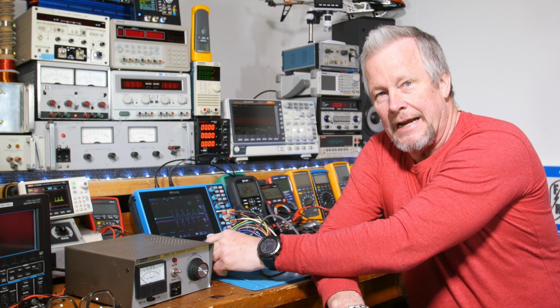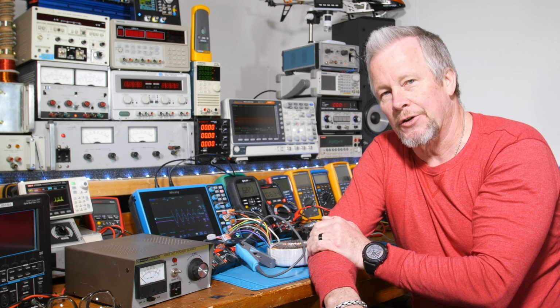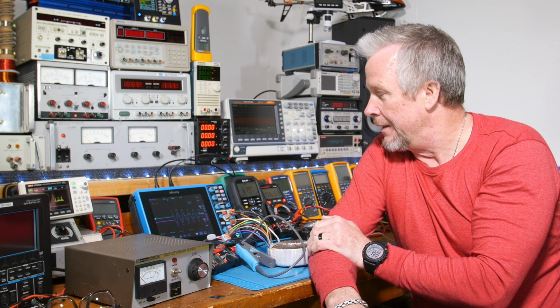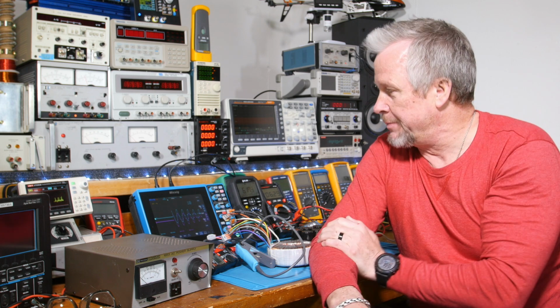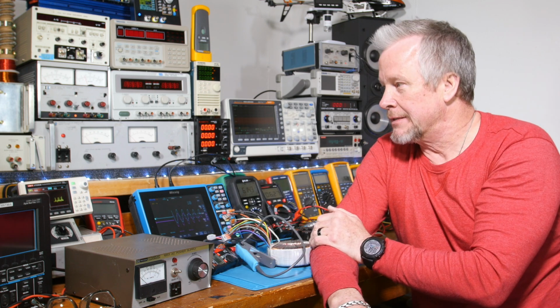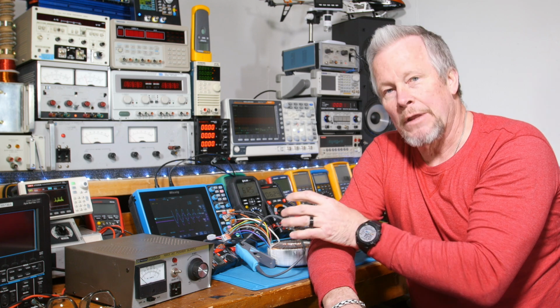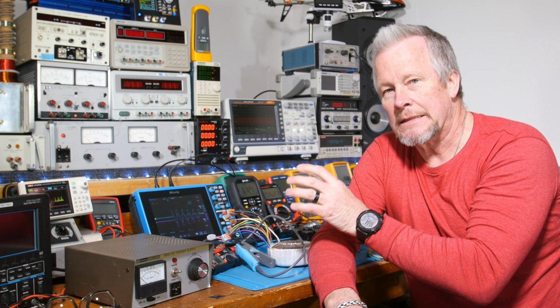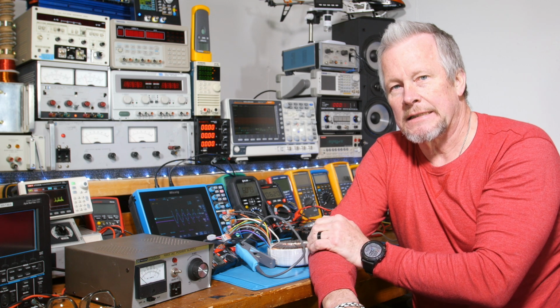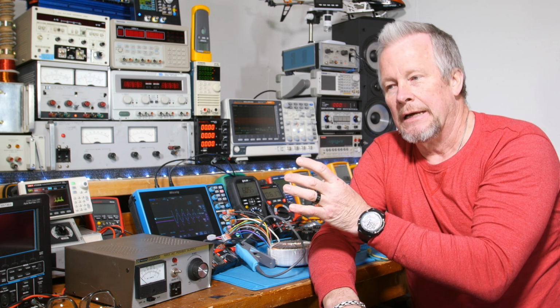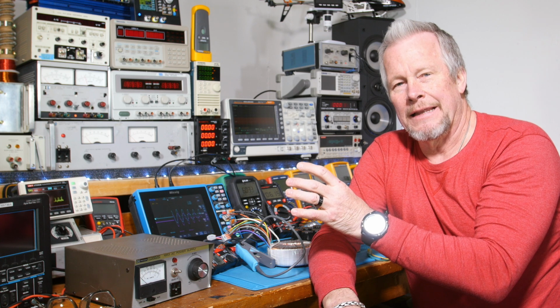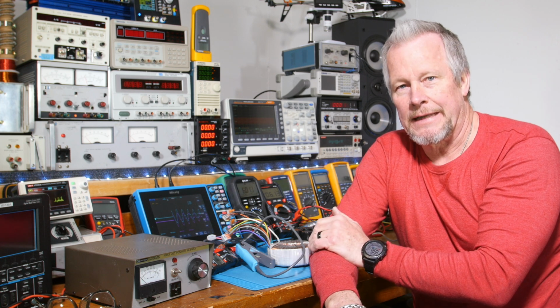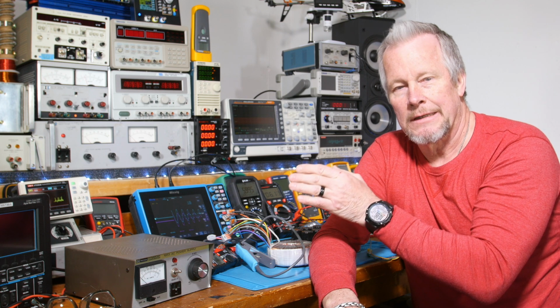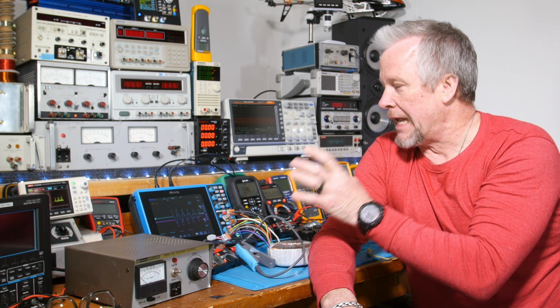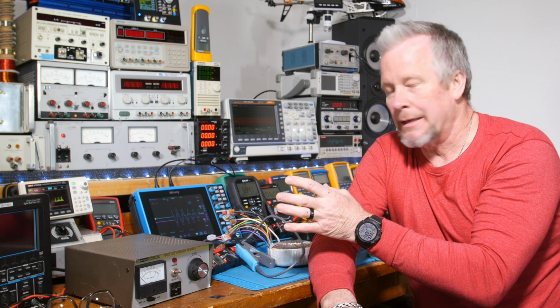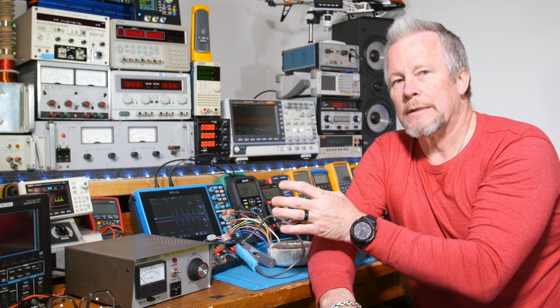Now, getting to the Kaiweets, I put that in there just to show you what it was doing, just to make a point. A lot of the meters, the bench meters or the current clamp-on meters, when you do that max measurement, they're all going to be similar. They're going to be around 100 milliseconds that they capture and sample, and they may only take 5 samples in that 100 milliseconds, so they're not even capturing the peaks maybe, but they'll capture enough samples and give you an RMS value of that.